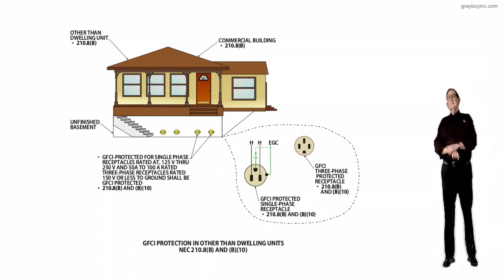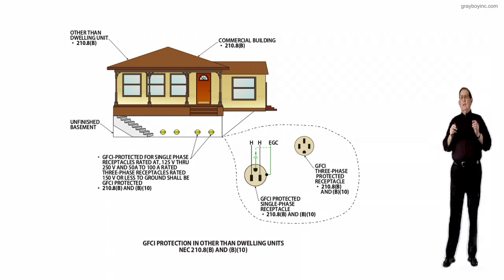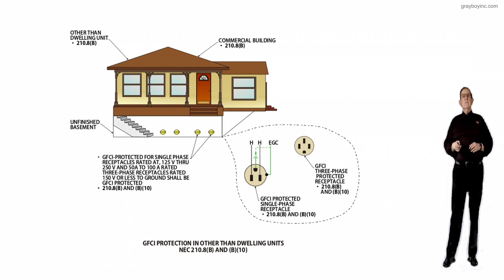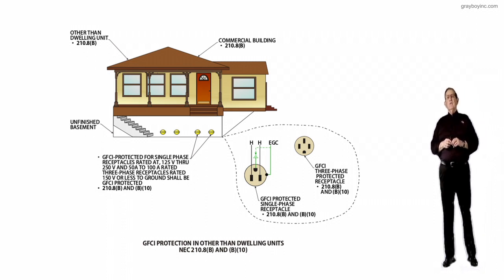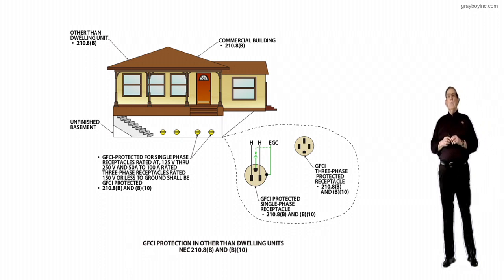Now, as kind of a reminder, 210.8A5 deals with dwelling unit basements, finished or unfinished, but notice this is unfinished only where you would have equipment that you had to cord and plug connect to circuitry that would give them more power than the 120-volt ground receptacles would provide.